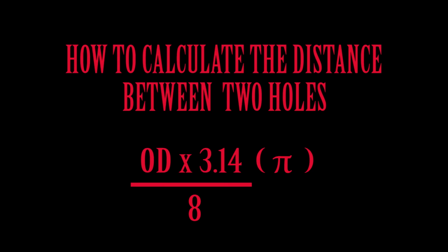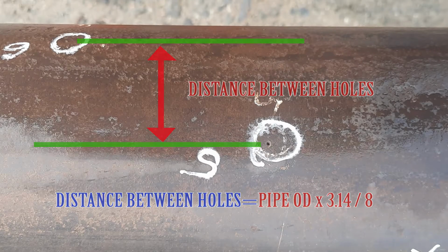So those 8 full penetrated holes in a spiral pattern cover the whole circumference of the standard pipe. The distance between each hole should be the same. These are simple techniques to find out whether the calibration pipe or standard pipe is manufactured under the criteria. The circumference is the pipe diameter times pi, 3.14, divided by 8. Then you can get the distance between two holes. You should ensure that these holes cover the whole circumference.